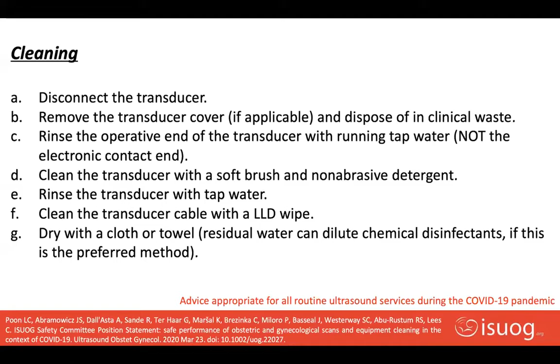Current guidelines for cleaning transvaginal transducers recommend using running water to remove any residual gel or debris from the probe before cleansing the transducer thoroughly using a damp gauze pad or other soft cloth and a small amount of mild non-abrasive liquid soap. The use of a small brush, especially for the areas of angulation, should be considered, depending on the design of the particular transducer. The transducer should then be rinsed thoroughly with running water and dried with a soft cloth or paper towel. Regarding disinfection, always refer to your facility's infection control policies and protocols, as well as the transducer manufacturer's instructions for use and labels for use.